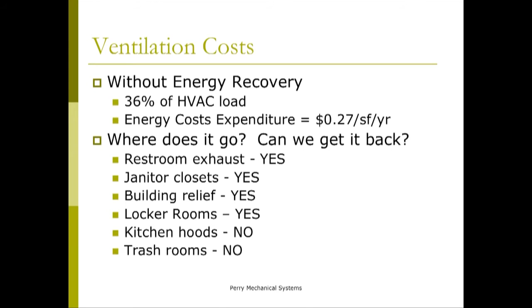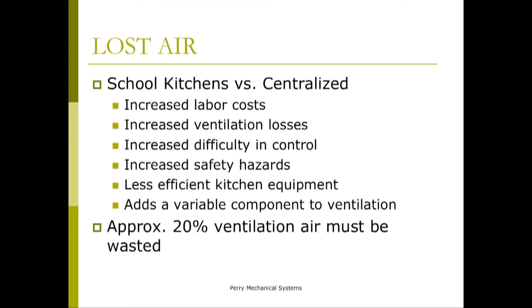Some air is just going to be lost, especially in a kitchen. You can't take the air coming off your kitchen hood and recycle it into the building; it's just not suited for that. So in program planning for something like a school district, think about the benefits of a centralized kitchen versus individual school kitchens. With a centralized kitchen for the district, you take that unrecoverable exhaust air out of each building and centralize it into one location. You also centralize your labor and expenditures. About 20% of your ventilation air ends up wasted in a typical school if you've got a kitchen there.